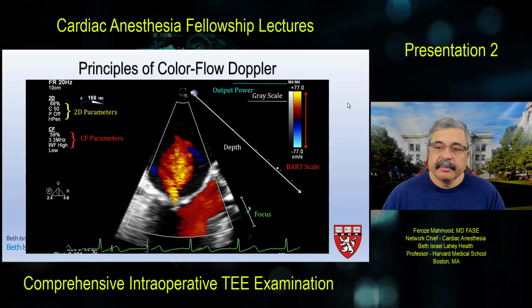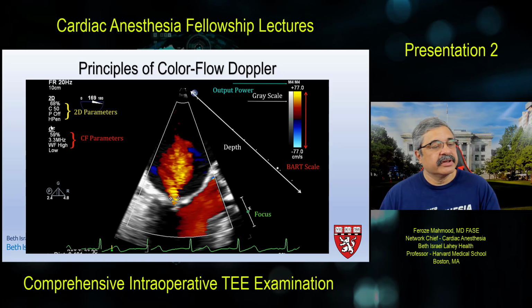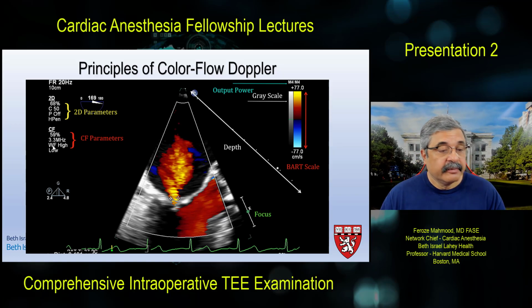If you look at a color flow signal, you can see this is the frame rate, this is the depth, these are the 2D parameters, which means the gain is 68%, the compression is 50, the persistence is off, and you're in the harmonics penetration mode, which means you want to see further into the tissues. Now this states the color flow parameters, which means your color flow gain, which is analogous to the two-dimensional gain, is 59%. Your frequency range is about 3.3 megahertz based on this penetration, because the sonographer wanted to see deeper structures. You have set your wall filters, which is the one we just talked about, demodulation and high pass filters, to very high, which means the high amplitude signals will be taken out, and your sensitivity is very low.